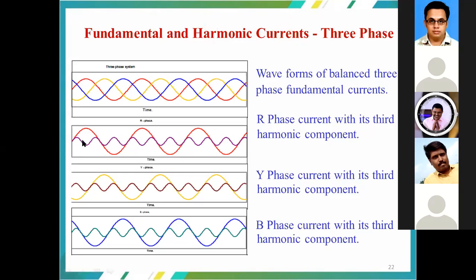So in the second one, the R phase is there. Simultaneously, we have the harmonics for the R phase, which is of the third order harmonic. How do we describe it as a third order harmonic? The fundamental component passes a single cycle, whereas the harmonic component, the unwanted signal, passes 3 cycles, therefore it is called a third order harmonic.